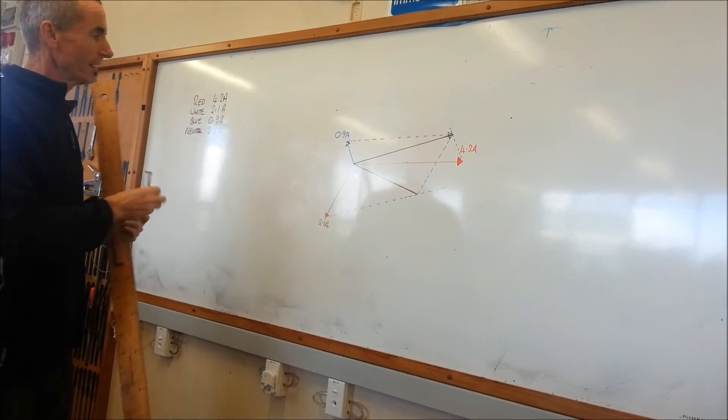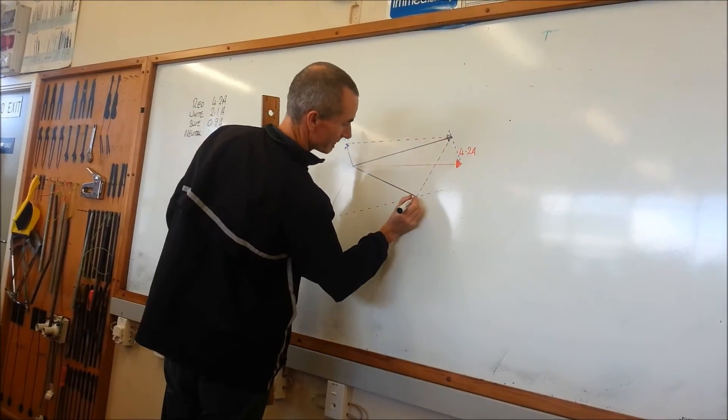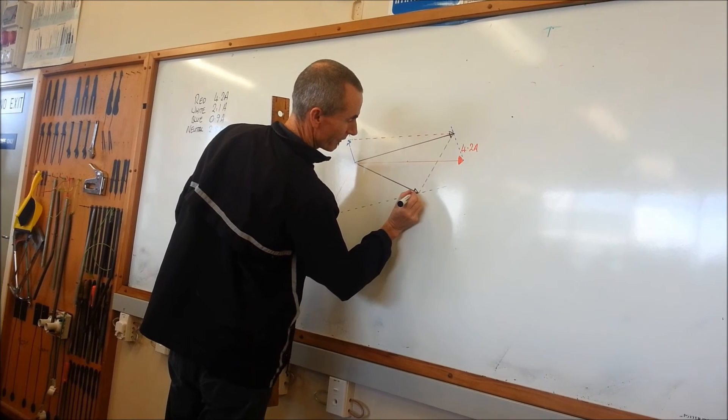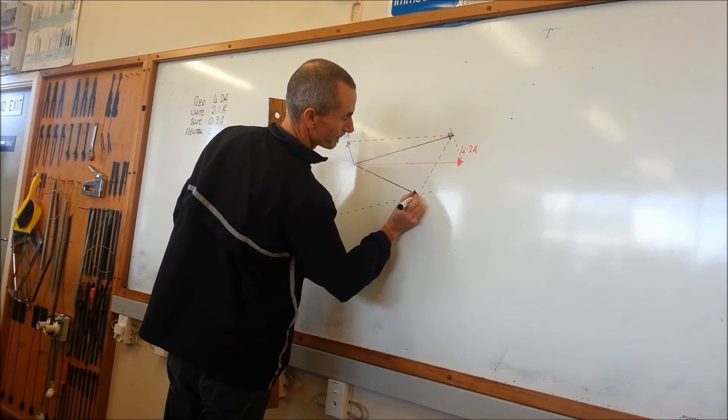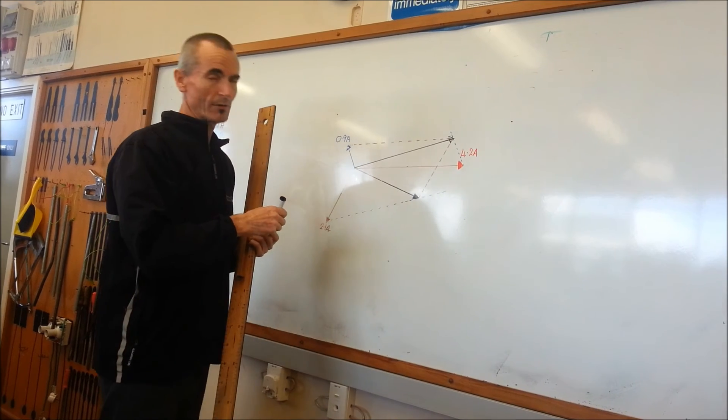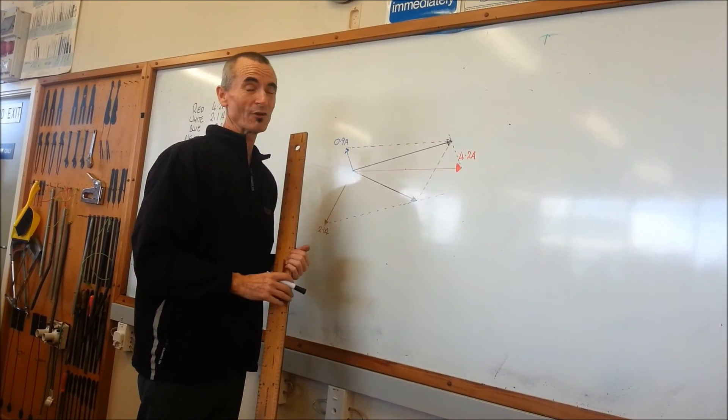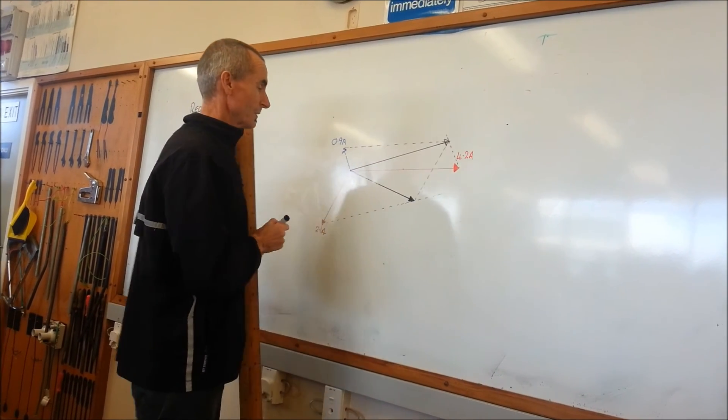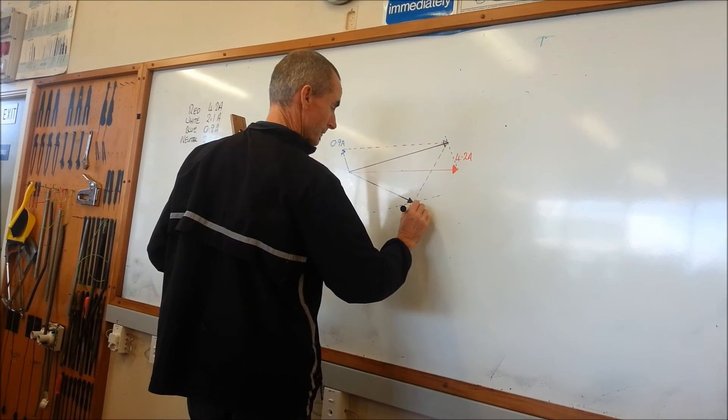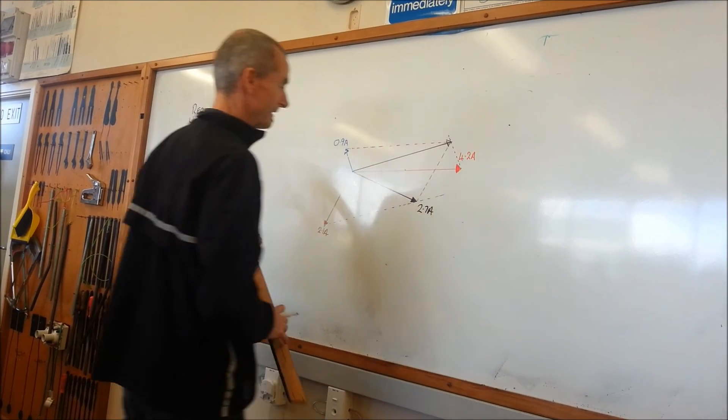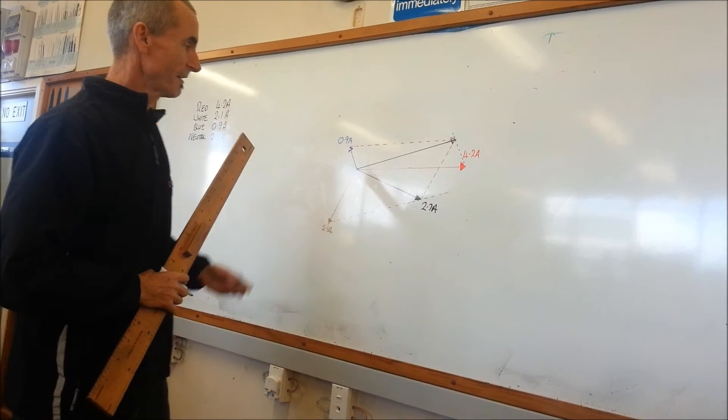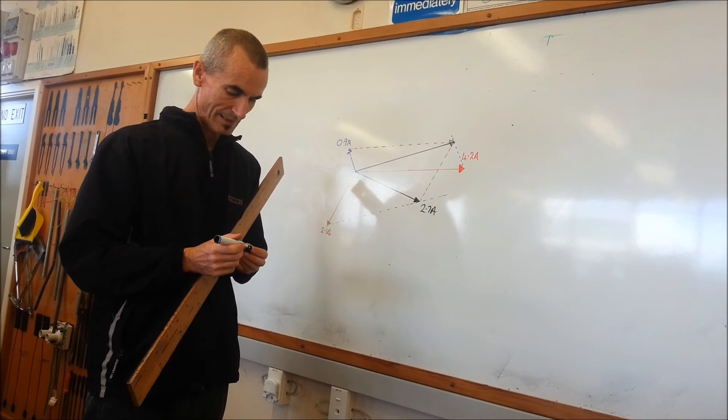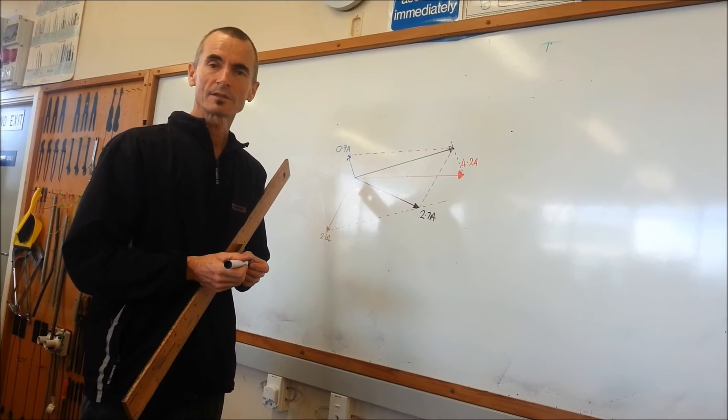Our calculation was 2.5, what we've drawn is 2.7. Now the variation can come about because it's not exactly 400 volts, it's not exactly 230 volts. But the measurement here we came up with is 2.7 amps and the reality was 2.5. So we're only talking 200 milliamps anyway. Close enough.